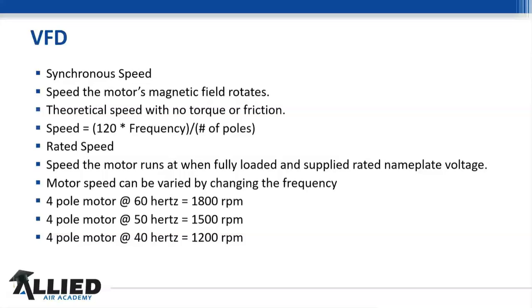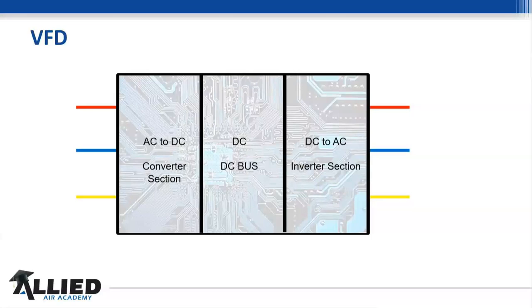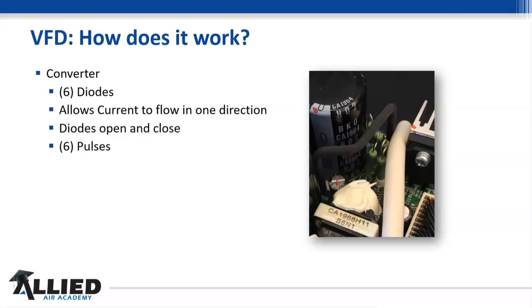So how does this thing work? Why did Kyle talk about the amp draws and the voltages last week? Because the VFD changes AC to DC, then it goes from DC back to kind of an AC. So there's a lot that's going on in here. And this isn't too much different from an actual compressor inverter board. If you look at the 20 series we've got and any type of the mini splits like we've got, this is kind of the same sort of technology here, only we're controlling a blower motor to do this. So this is a brief synopsis of what goes on, and I want to go into it a little bit deeper so we'll understand the importance of how all this works.